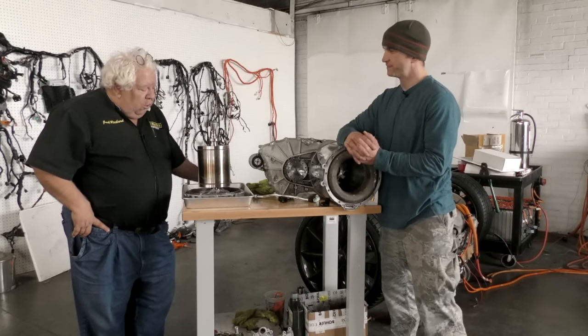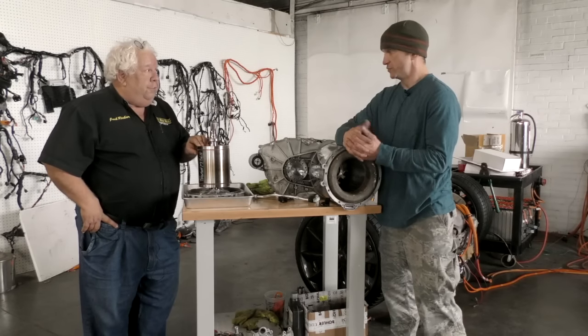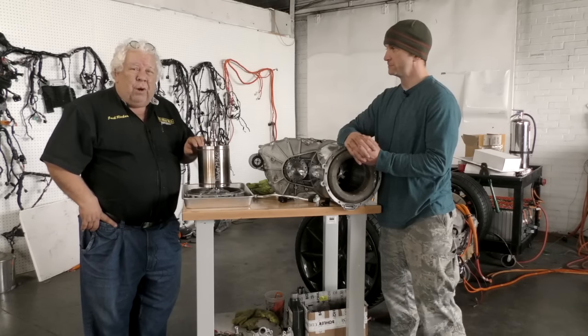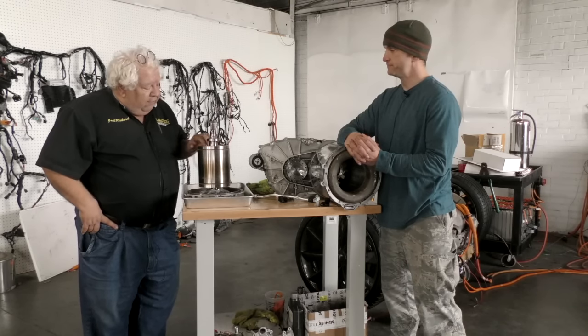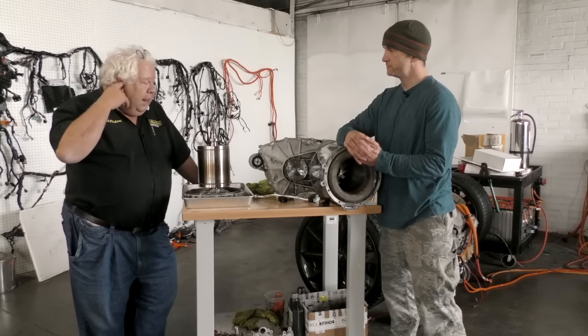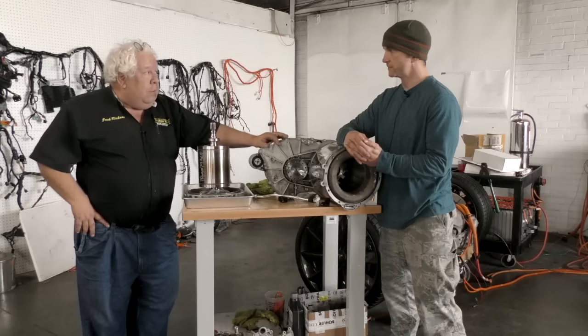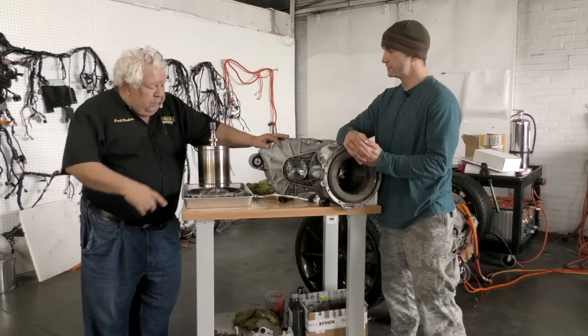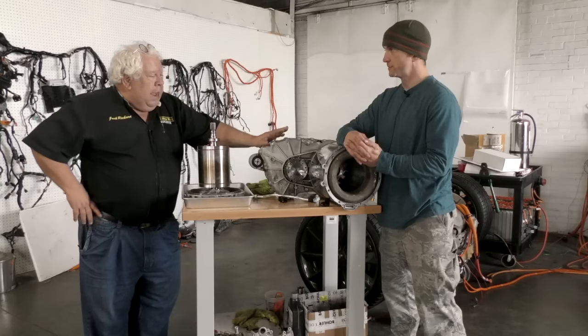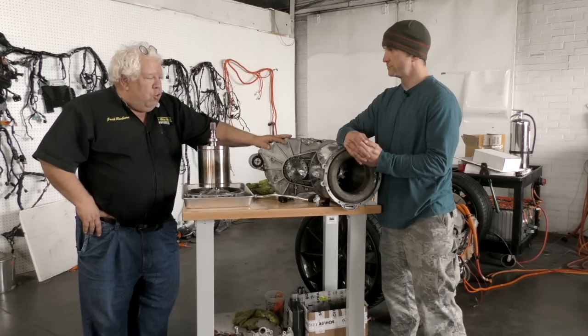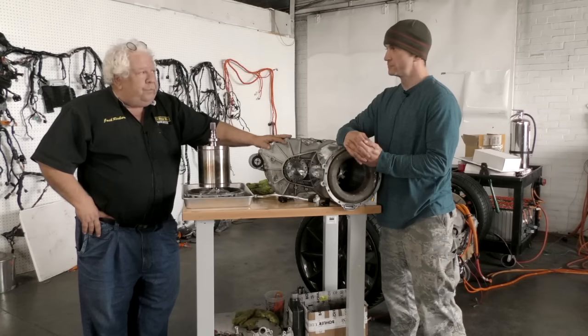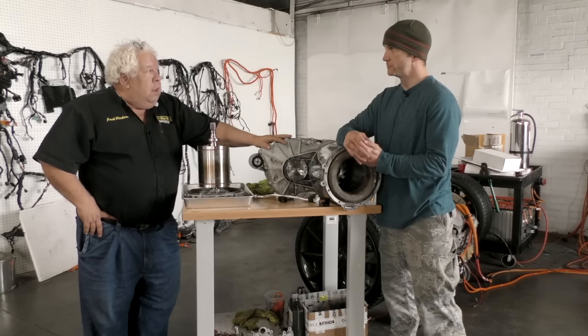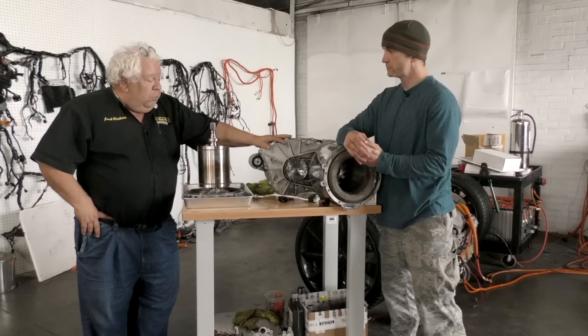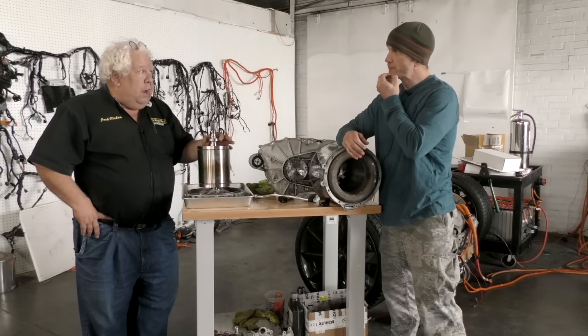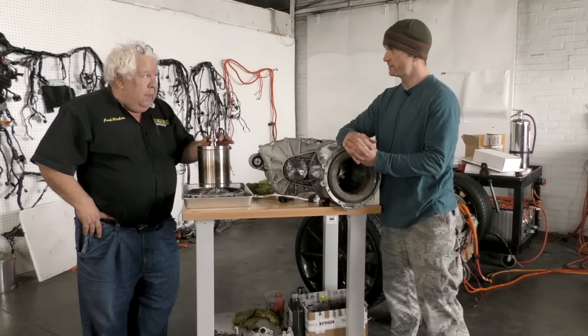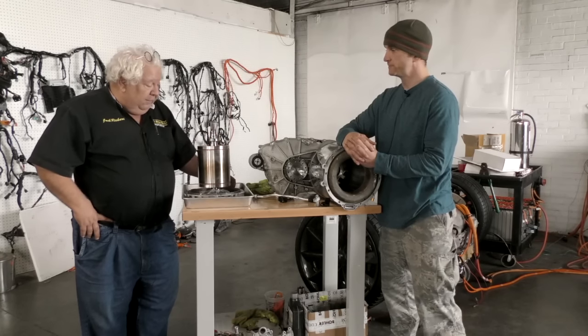Tom's theory is that inducing currents in the rotor, you also induce voltages. Ohm's law kind of requires it. So we have a voltage in the rotor and a differential between the rotor and the case, which is normally grounded. You have to have some current flow in order for that to resolve itself, and the bearings are not a very high resistance path. Metal to metal contact, metal balls, metal rim races.